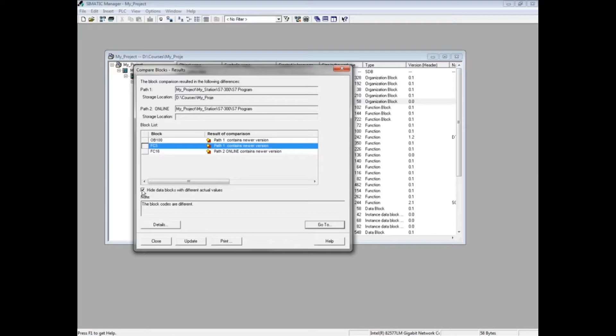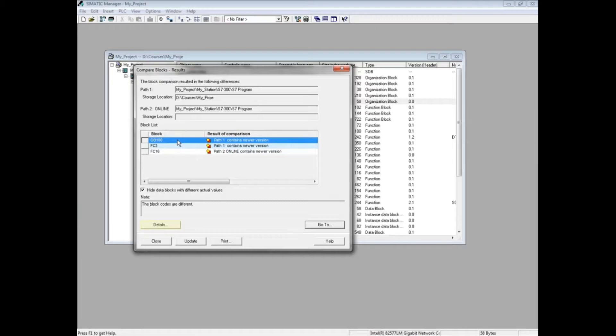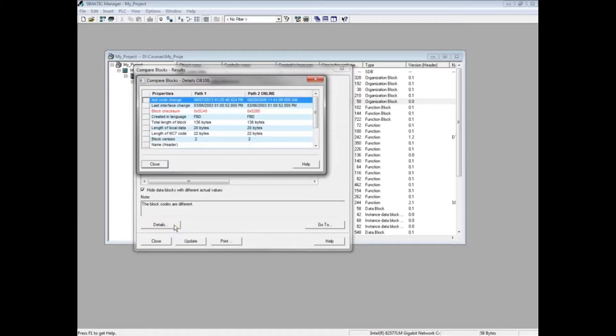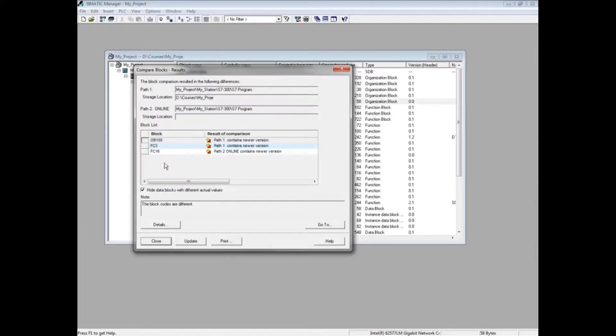Path 1 is the offline project storage location. Path 2 is the online PLC program. In the comparison list, OB 100 says that Path 1, the offline project, contains a newer version. Highlight the OB 100 block. If you would like to see a description of differences, click the Details button. The details window shows timestamps, interface changes, size and length changes, and so forth. Click the Close button.